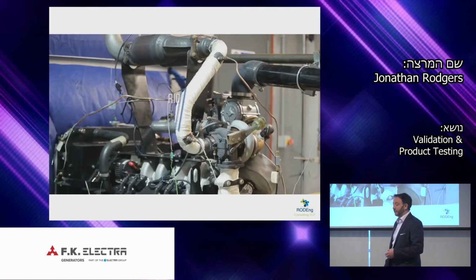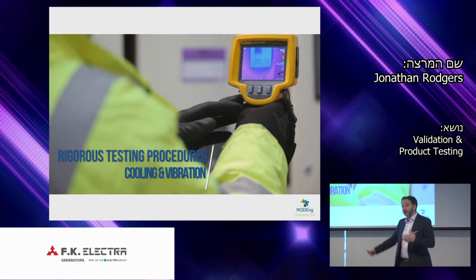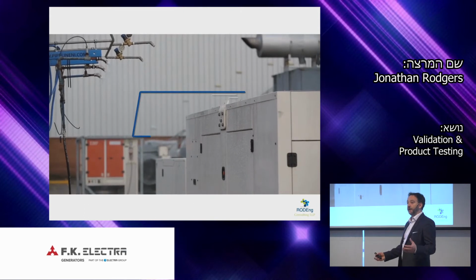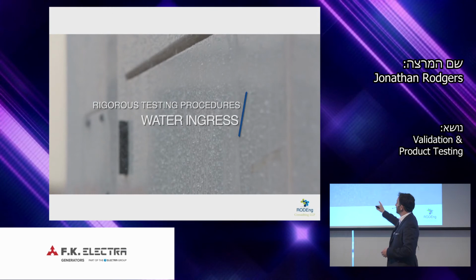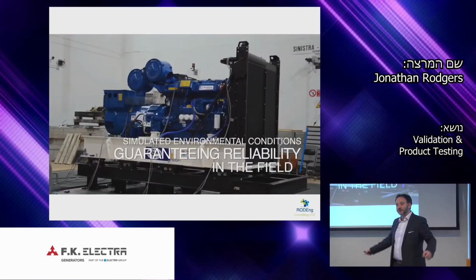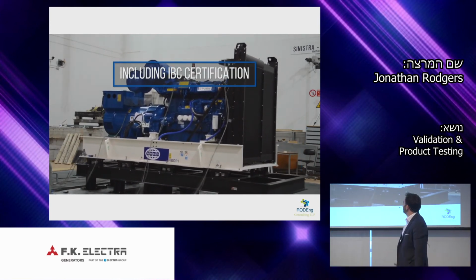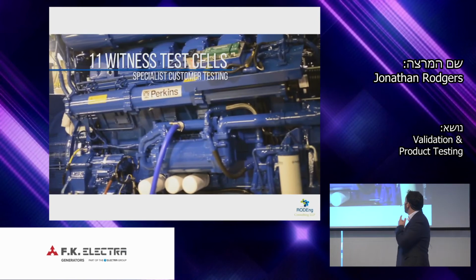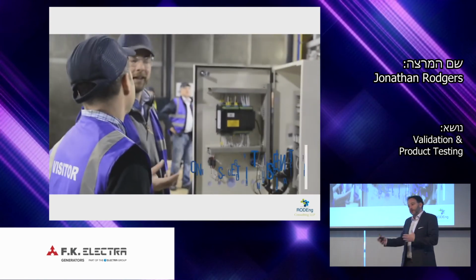But we test everything down to fuel consumption and emissions. We're looking at heat through our connections and on our cabling connections, and management of that heat through the insulation. We have water ingress tests. When I was a 20-year-old kid testing generators, a water ingress test was a big bucket with holes in it. It's not like that now, it's very automated. These are our vibration tables. We do seismic testing. All of this leads into the development of the product, but we don't finish there.